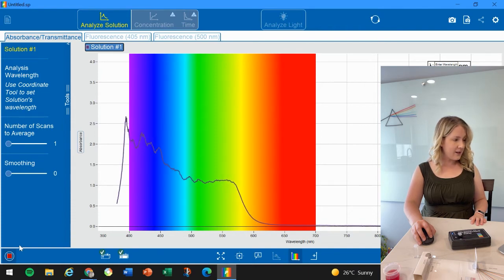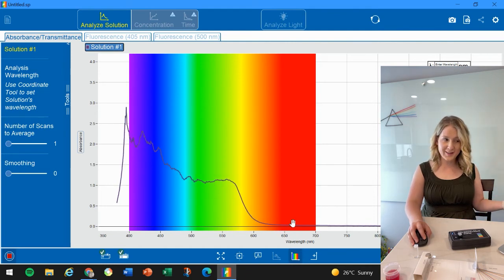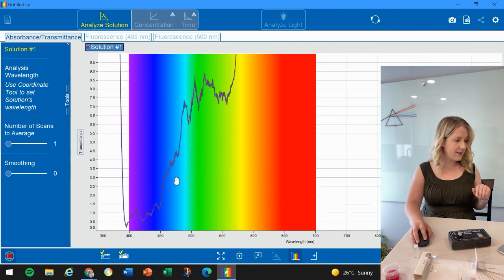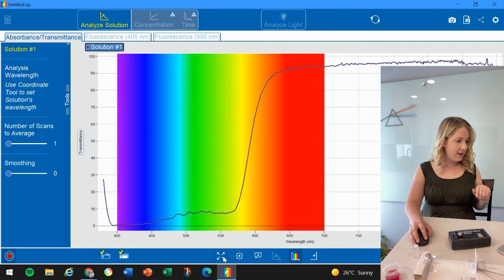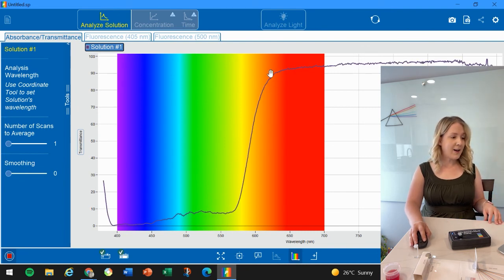And you can see here in terms of absorption, it's absorbing a lot of light in the violet down to the yellow range. And then we see a big drop off in the orange to red, of course, because this is red. If we want to flip this, we can just click here on transmittance, and we would get the opposite effect. So it is not allowing really much violet, blue, green, yellow light to transmit through, whereas plenty in the red range of the spectrum.